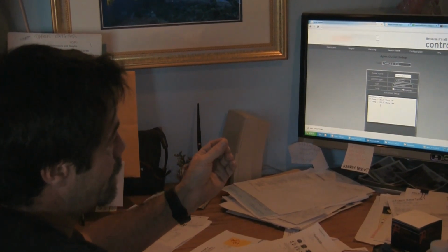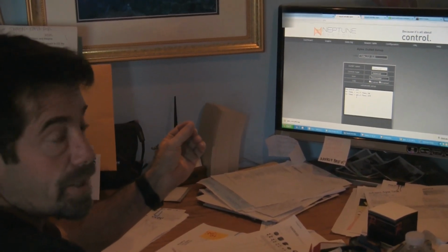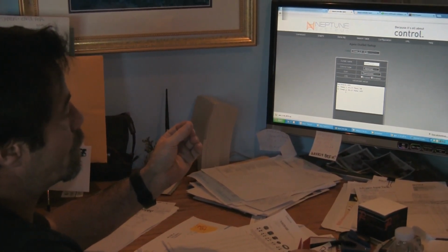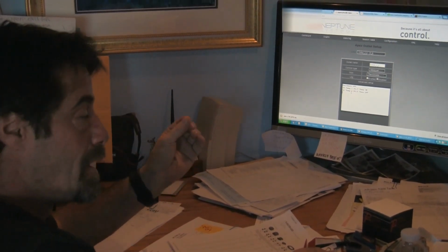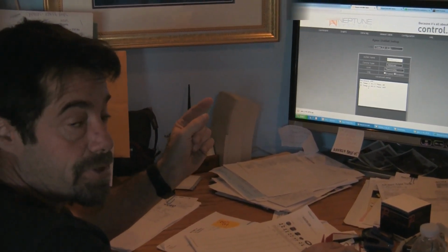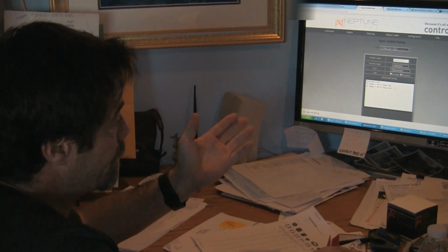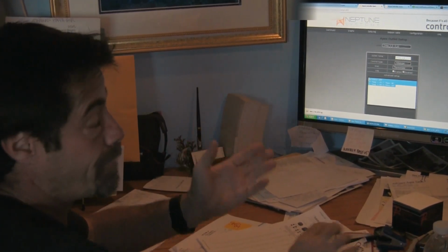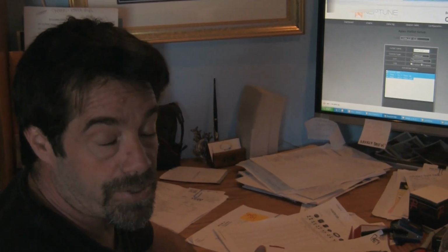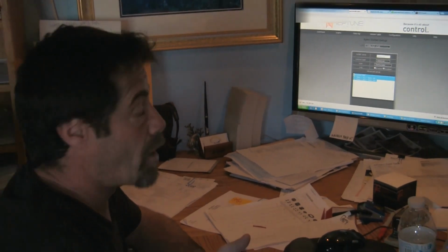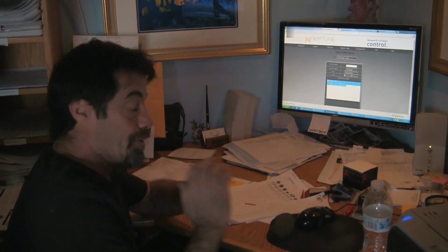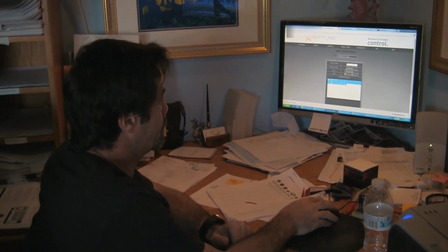So the chiller outlet, which is acting as a failsafe, the chiller will get power at 81.7 degrees and lose power at 80 degrees. At 82 degrees, the thermostat on the chiller will turn it on. So effectively the Apex is acting as a failsafe in case the thermostat on the chiller sticks. His tank will never drop below 80 degrees, and the outlet to the chiller will automatically shut off.